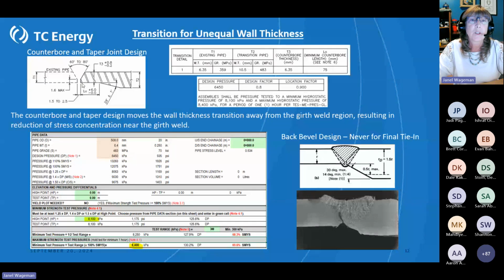We calculate the counterbore length, L0. This is a calculation because the highest stress point in this design is right at this transition point where it starts to taper. So we want to keep this stress point as far away from the weld as possible within machining capabilities—that's why we define this L0. This information would go to the fabrication shop saying we need a counterbore of 75 millimeters.